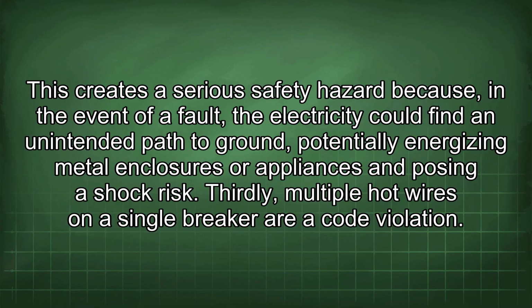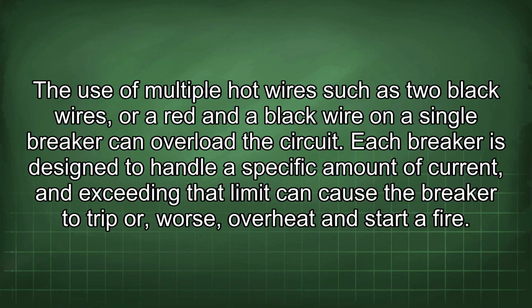Thirdly, multiple hot wires on a single breaker are a code violation. The use of multiple hot wires, such as 2 black wires or a red and a black wire, on a single breaker can overload the circuit. Each breaker is designed to handle a specific amount of current, and exceeding that limit can cause the breaker to trip or, worse, overheat and start a fire.